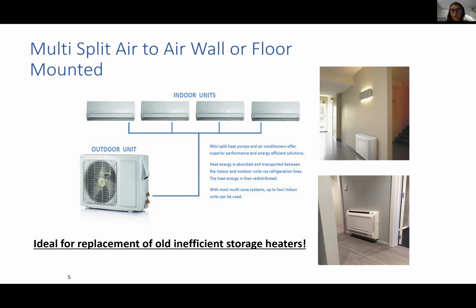But recently, in the last probably 2 years, these have started to become quite popular for residential solutions, and specifically in retrofit scenarios where there are existing storage heaters. So in small local authority and social housing units where there's storage heating and it's going to be too disruptive to dig up floors and put in radiators and an air-to-water heat pump, this is a really good solution because the pipes can be run at high level. And we use these high wall units that you would see in, say, an apartment in Spain when you go on your holidays for air conditioning. This system is called a multi-split. You can have up to 5 indoor units connected to 1 outdoor unit.